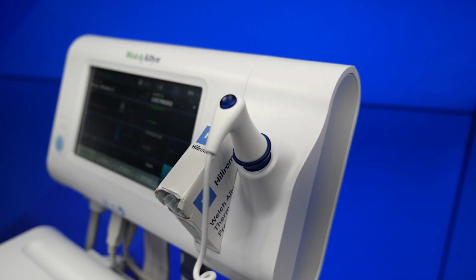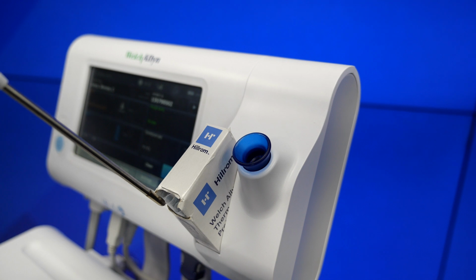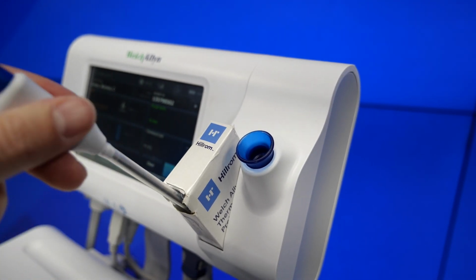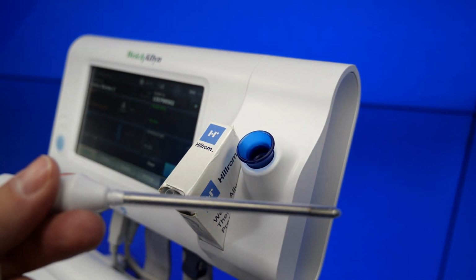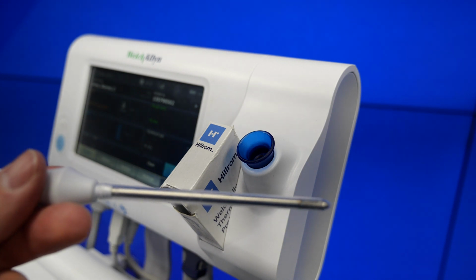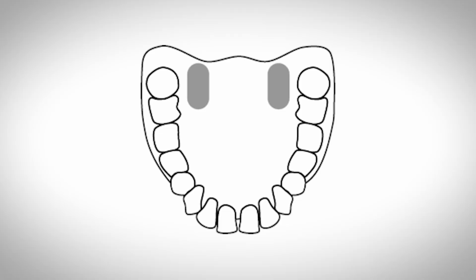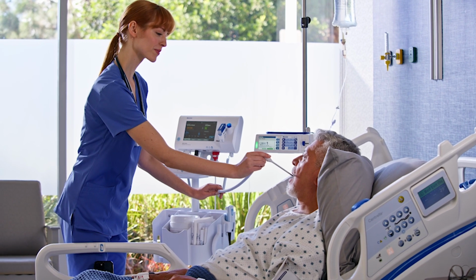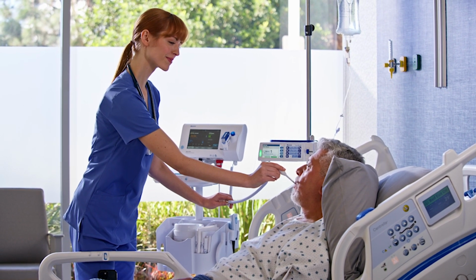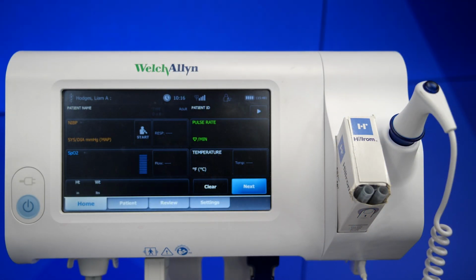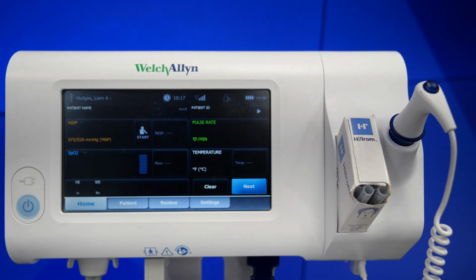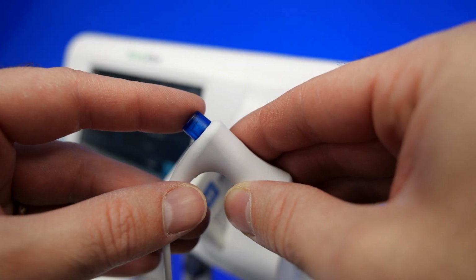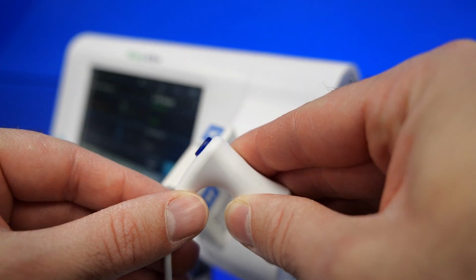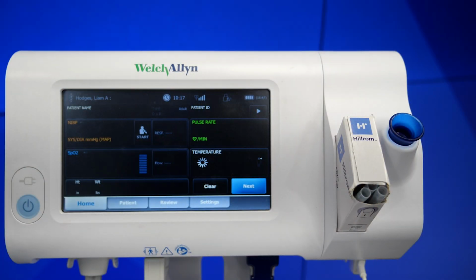Attach a cover to the probe by gently pushing down until the top blue button of the probe extends out. The device will beep indicating it's ready to take the measurement. Place the thermometer probe tip under the patient's tongue on either side of the mouth to reach the sublingual pocket and ask the patient to close their lips. At the end of the oral measurement, there will be 3 short tones. You can then remove the probe from the patient's mouth, discard the cover by pressing the ejection button, and then return the probe to the probe well. The temperature will then be displayed on the Home tab.